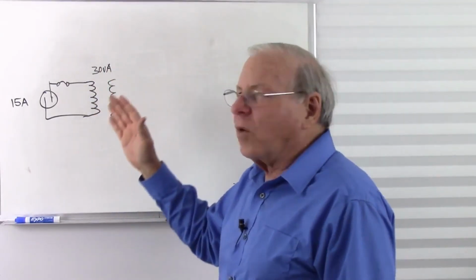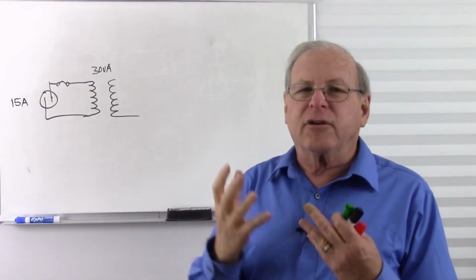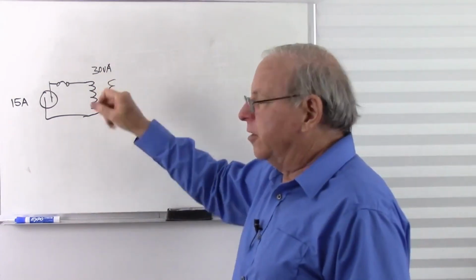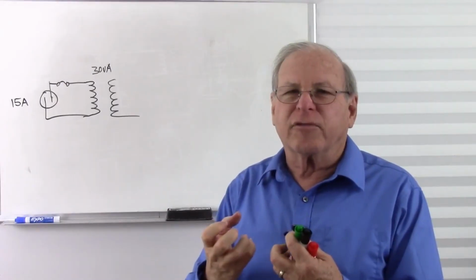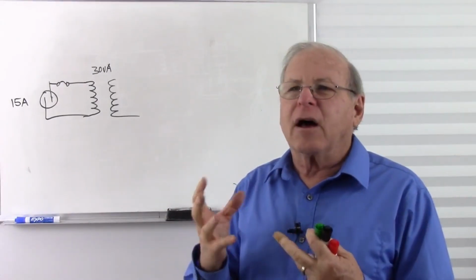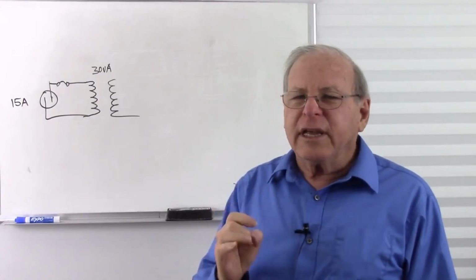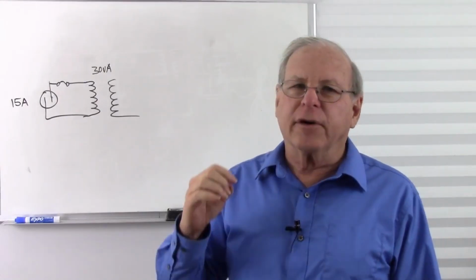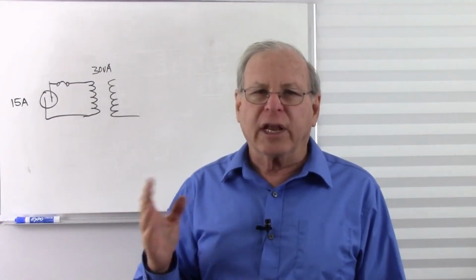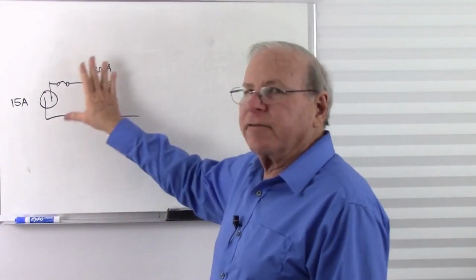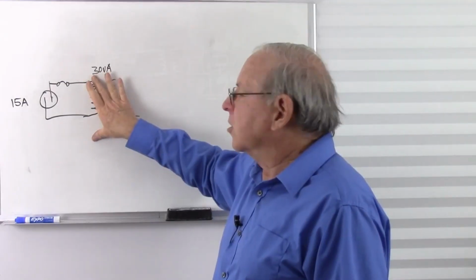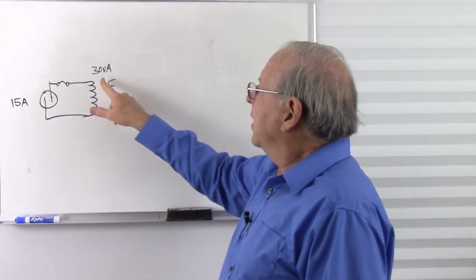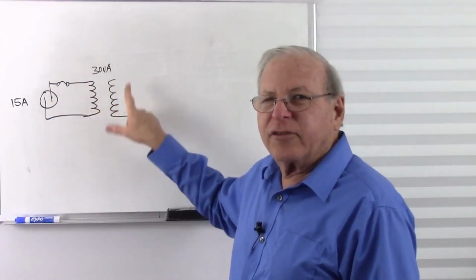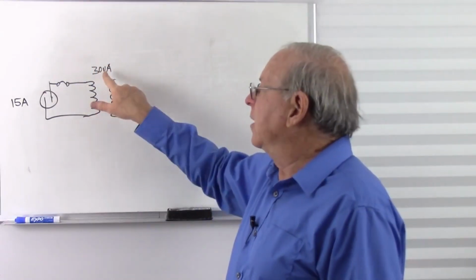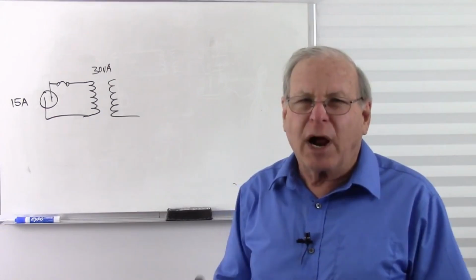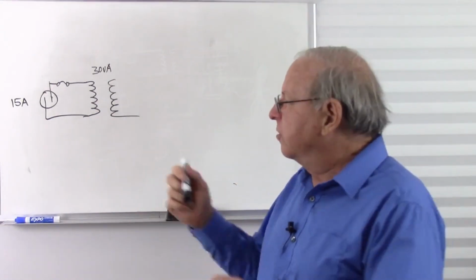Well, they don't call it watts because transformers do not consume energy except for a little bit of waste in the core, because the little bit of current flowing in there and the magnetic fields through there cause the core to get a little hot. You only have power if you have one of three things: either heat, mechanical motion, or electromagnetic radiation. And you get none of those from a transformer, just a little bit of warmth from the core. So it's improper to say that there's any watts being dissipated here, so they're often rated in volt amps instead of watts, which is the proper way to do it. You might see them rated in watts, but usually volt amps.